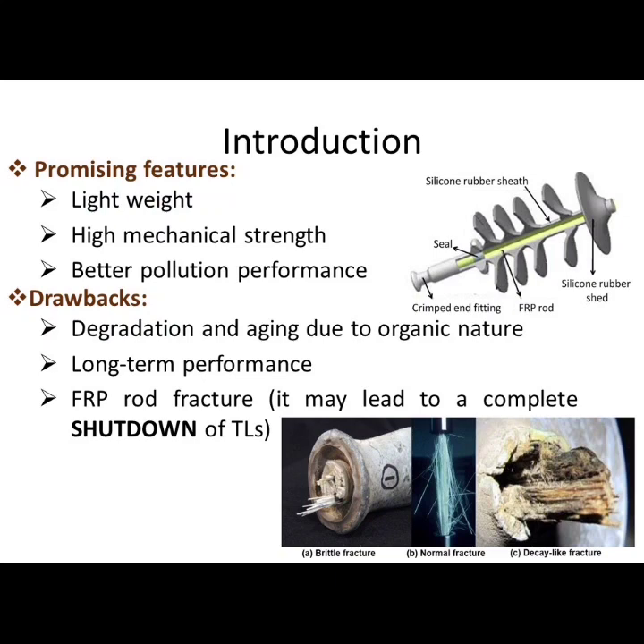Silicon rubber is made of PDMS with some added inorganic filler like ATH or silica fillers to improve the mechanical and electrical characteristics, whereas the FRP rod is made of epoxy resin matrix with glass fiber. However, these new insulators show some drawbacks, especially in long-term performance and reliability: degradation and aging under the action of electrical discharges due to the organic nature, electric field enhancement near the end fittings, especially the high voltage end, and also FRP rod fracture, which may lead to a complete shutdown of the transmission line.